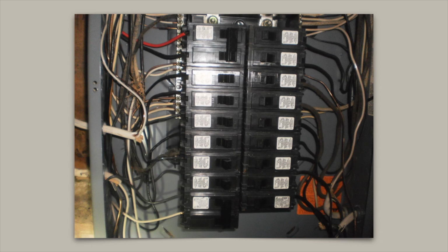One point needs to be emphasized. A wire will only carry the current that is specified by the load. If you turn on a light bulb that draws 1 amp, and it is the only load in the whole house, then the most that would be on any cable throughout the house is the 1 amp. The amount of current on a wire depends on how much current is being drawn. We see the wrong size breakers on the wrong gauge wires all the time. There may never have been the current going through that would overheat the wires, but that does not mean that the wires are safe. Always check your wire size and your breaker size.